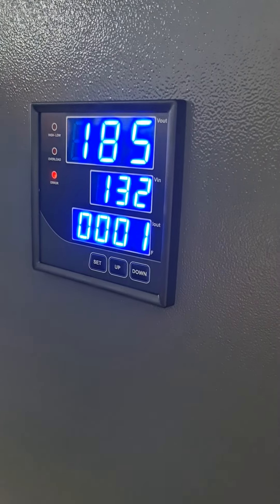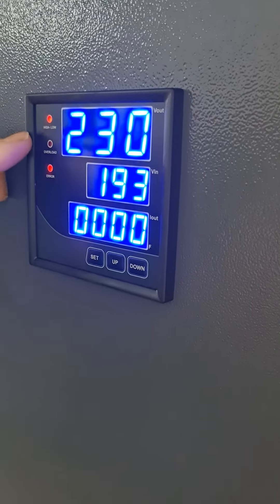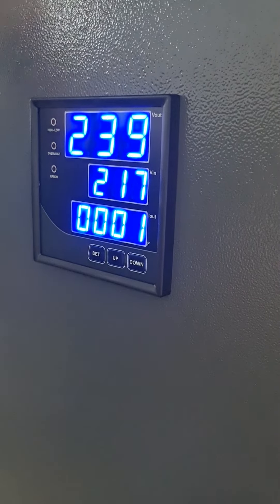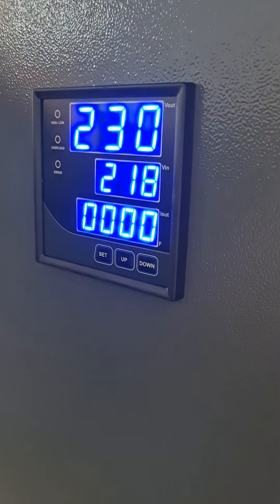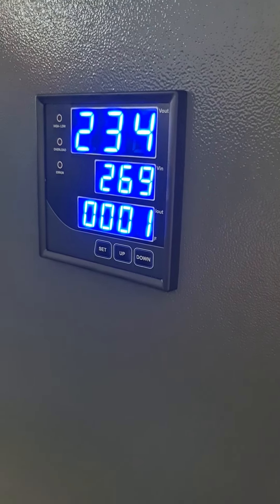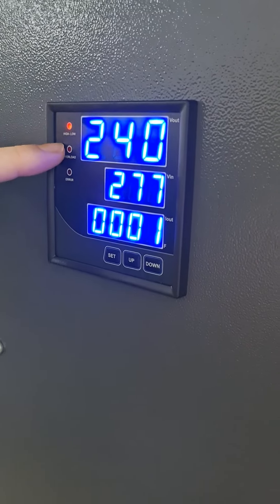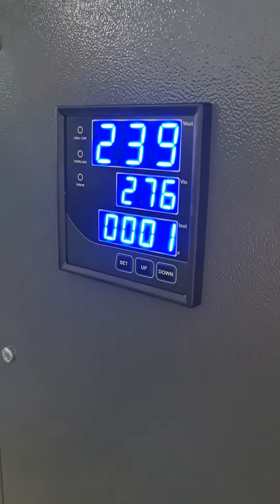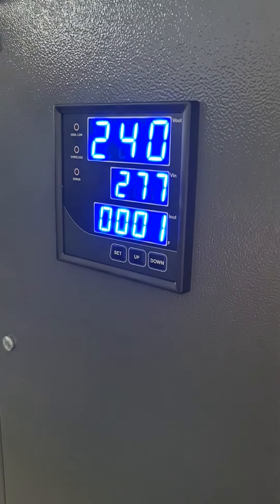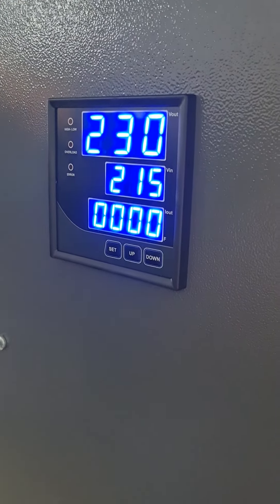When we increase the voltage up to the regulation range, as you can see the output voltage is back to normal, so the contactor is now on and the device is active. We are increasing the voltage now — it's at the upper limit. The device has increased the output voltage and a few seconds later it will switch off. Now we are back in the normal range of the input and the device is operating normally.